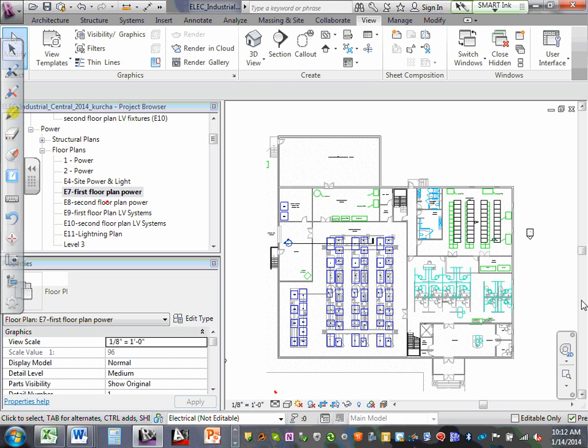At least the copy that I have. The building is fully sprinkled, so full smoke detector coverage is not required. If you want smoke detector coverage, it's over and above the requirement of the code. And if you're going to provide smoke detection, you've already got it here in the manufacturing area with the beam detection, right? Now, what you would do is you would just be applying smoke detection in the office areas, corridors, and the other rooms on 30 foot centers. 15 feet from each wall, first device, and 30 foot.